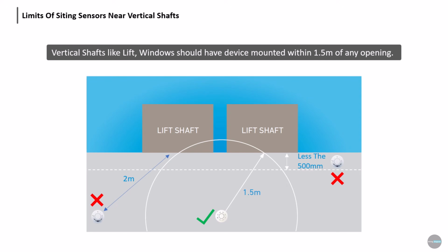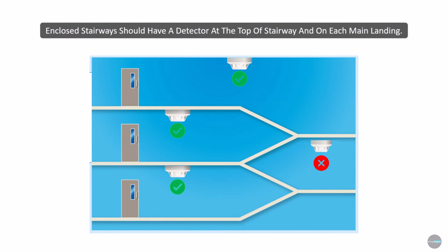Limits of siting sensors near a vertical shaft. Friends, if a building has a lift, windows, or closed stairways, the detector should be installed within a 1.5 meter radius of the lift shaft or window. This is because during a fire, smoke always travels toward windows, lift shafts, or any vertical openings in the building. So to ensure the detector properly senses the smoke during a fire, we install it close to these areas. And if there is a closed staircase, then the detector should be installed at the top of the staircase and the main landing area.